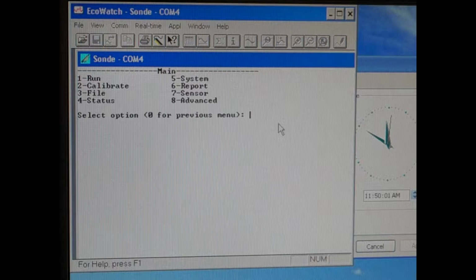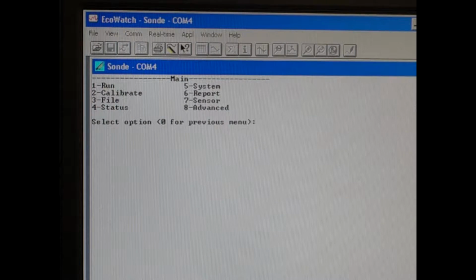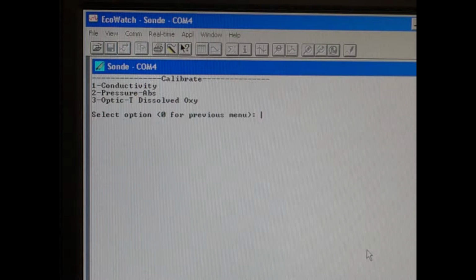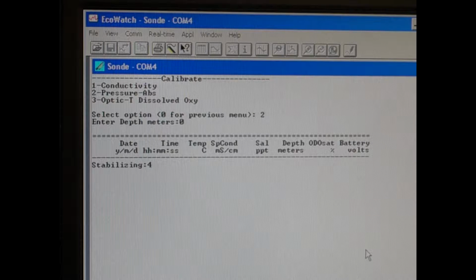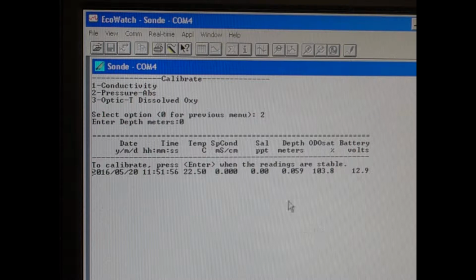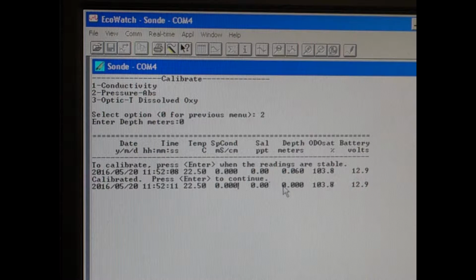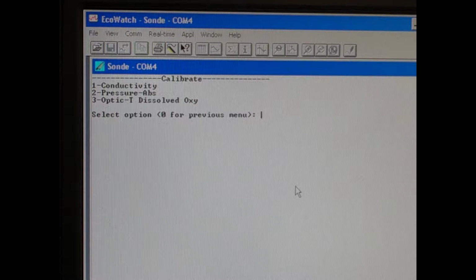So I can move back up to the main menu. Now we're going to calibrate depth on the Sonde. So I'm going to go to 2 for calibrate, and it's going to be under pressure, number 2. And enter depth in meters. Right now it's in the air, so the depth is 0. Push enter, and it's going to come up with the window that it's going to stabilize. And right now the depth is 0.06. We're going to write that value down on our calibration sheet for the pre, and I'm going to push enter. So now that calibrates it. This is the post, 0.0. So I push enter, and now that's calibrated.